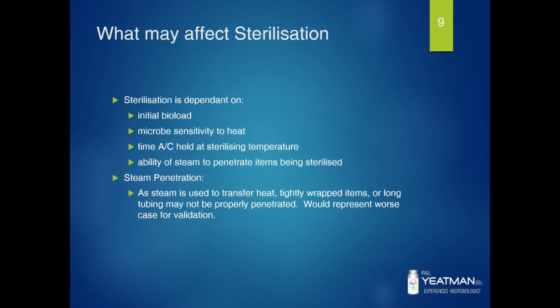What may affect sterilisation? Well, sterilisation is dependent on a number of factors. The initial bioload, the microbe sensitivity to heat, the time the autoclave is held at the sterilising temperature, the ability of steam to penetrate the items being sterilised, and with that, as steam is used to transfer the heat, tightly wrapped items or long tubing may not be properly penetrated, as would containers which are integral, say a Schott bottle with a tied-on lid. You can't get steam penetration in there, which means that the heat transfer isn't as good, which I'll discuss.